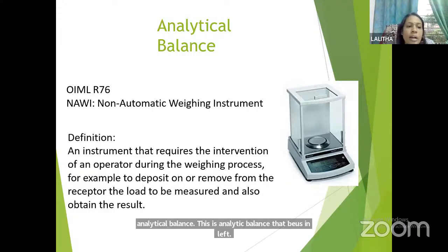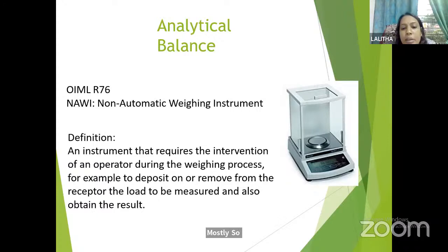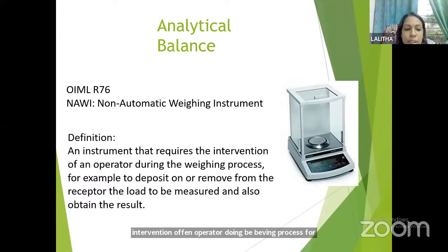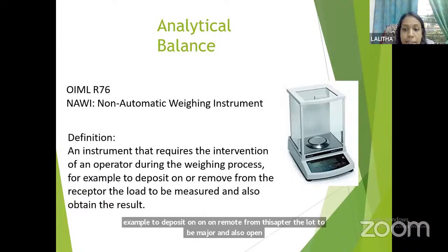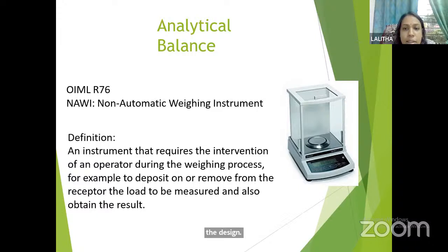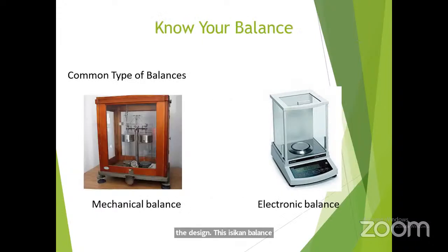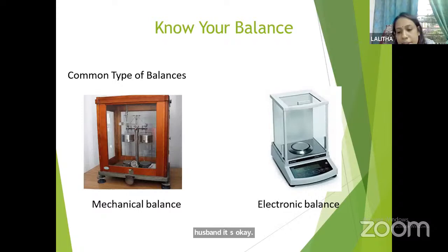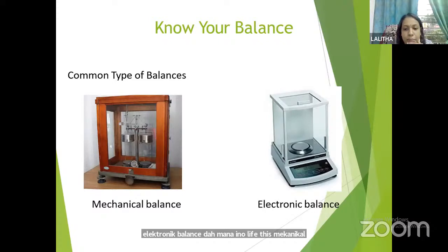So now we call it a non-automatic weighing instrument. Definition: an instrument that requires the intervention of an operator during the weighing process, for example, to deposit on or remove from the receptor the load to be measured and also obtain the results. This is an analytical balance. I'm sure most of you have seen this. A common type of balance. This is a mechanical balance, and this is an electronic balance. The one on your left is the mechanical balance, but mostly we use electronic balance.